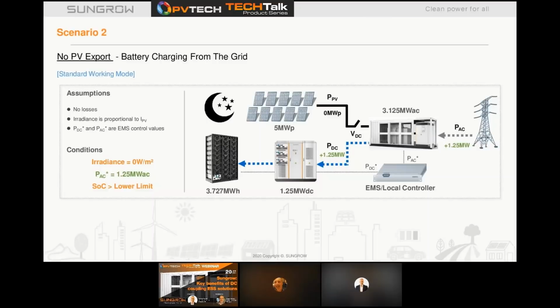Scenario 2, we have the PV plant with no PV export, battery charging from the grid. And as you can see from the graphic, it's nighttime. So the PV plant switches are disconnected. Again, this scenario is considered to be a standard working mode. In this situation, the state of charge of the battery is low, power is drawn from the grid to recharge the batteries. The battery can charge and discharge throughout the night.